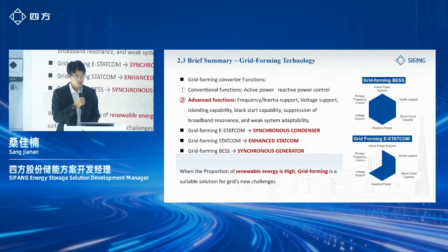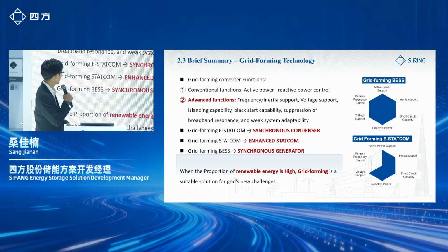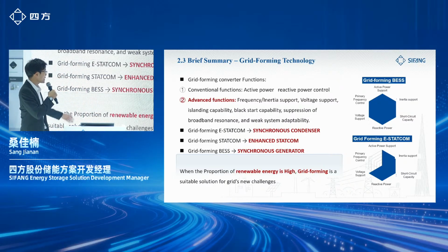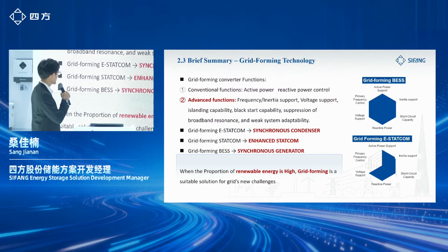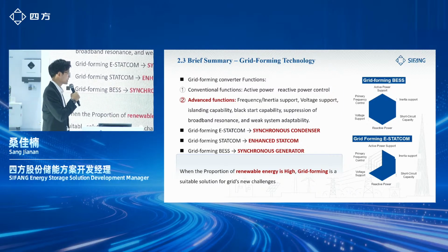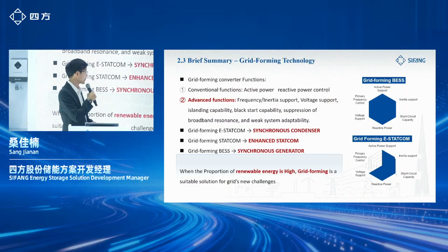And now to make a brief summary, we can see from here, the Grid-Forming E-STATCOM is just equal to a synchronous condenser, right? And the Grid-Forming traditional STATCOM is like an enhanced STATCOM, because we just oversize the capacitor on the DC side to make it available for overload. And the last one is Grid-Forming BESS. It can be equal to a synchronous generator.